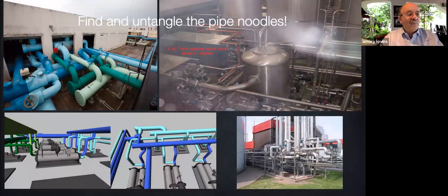More often, we see these kinds of pipe noodles all crammed together as if the installers were paid by the elbow, which I guess they more or less are. In the brewery at the upper right, I found the red traced pipe starting at the upper left could have had 11 fewer elbows if the installer had rotated the tank at the upper left by 30 degrees around its vertical axis before plumbing it, and then run a diagonal straight to the destination. Looking at the chillers at the lower left, just imagine how many fewer elbows there would be if the chillers and their headers were at about the same vertical level.